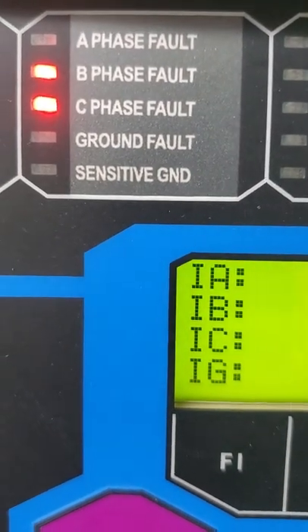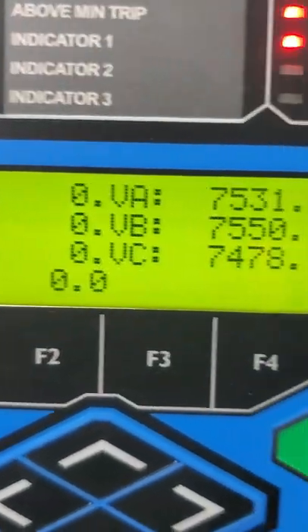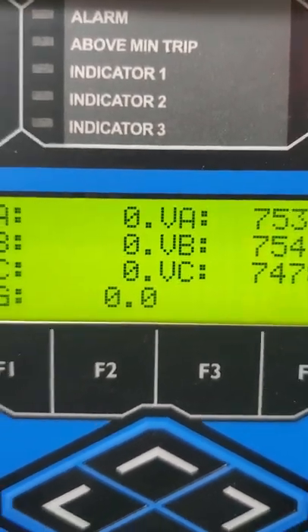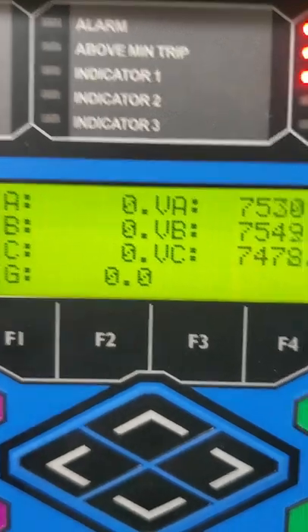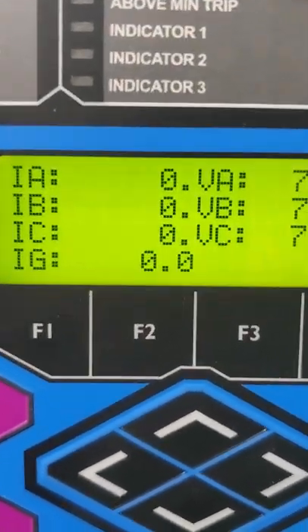So I can't show you guys much on the screen, but we've got the B and C phase fault — you'll see that right there. I could go in the event history, but we're just going to close this guy in. We've got permission from our dispatch. You're going to see the current spike right here as soon as that closes in.